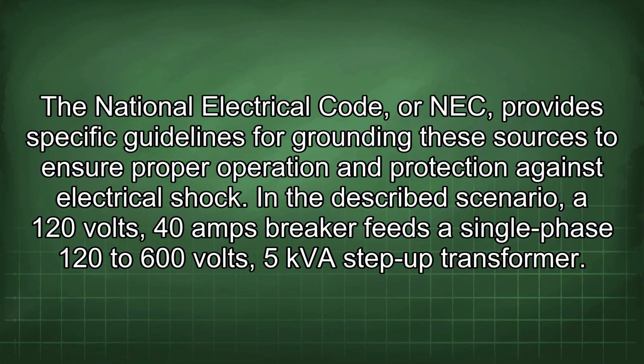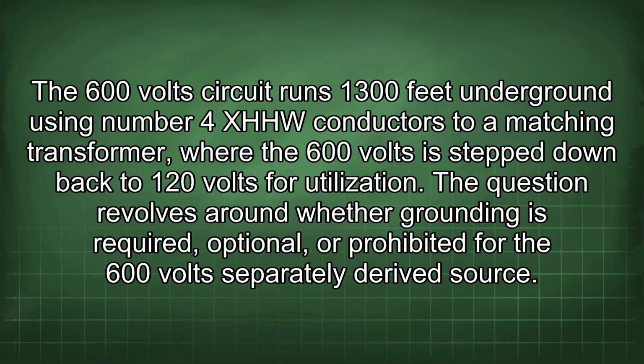electrical shock. In the described scenario, a 120 volts 40 amps breaker feeds a single-phase 120 to 600 volts 5 kVA step-up transformer. The 600-volt circuit runs 1300 feet underground using number 4 XHHW conductors to a matching transformer, with the 600 volts stepped down back to 120 volts for utilization. The question revolves around whether grounding is required, optional, or prohibited for the 600-volt separately derived source.